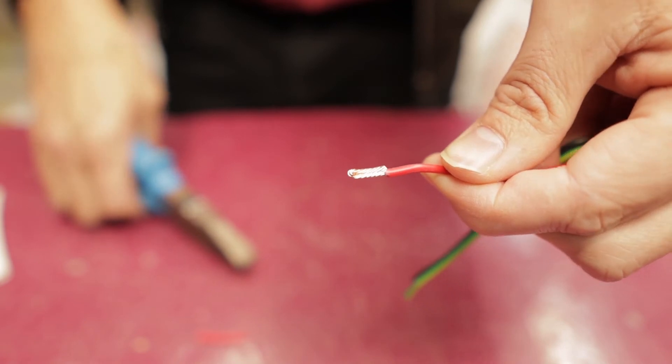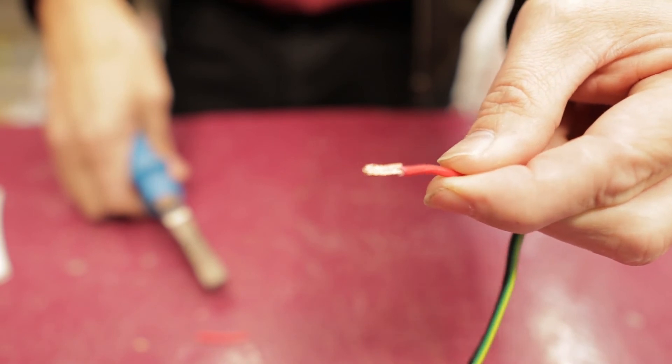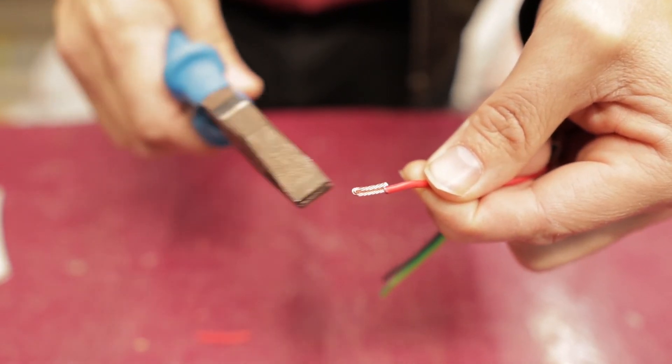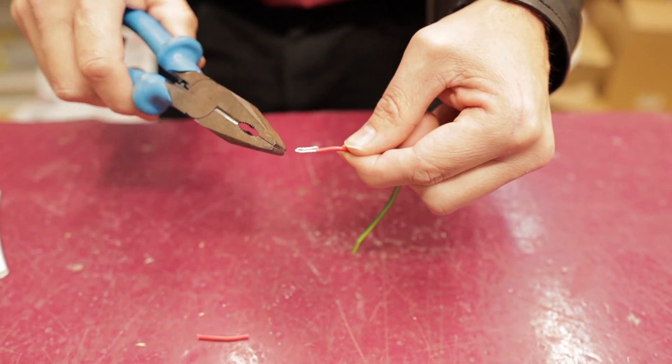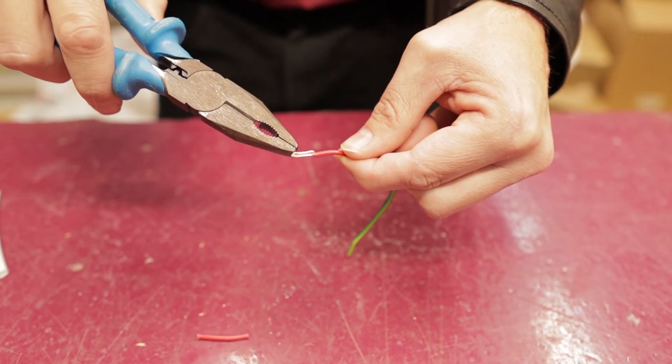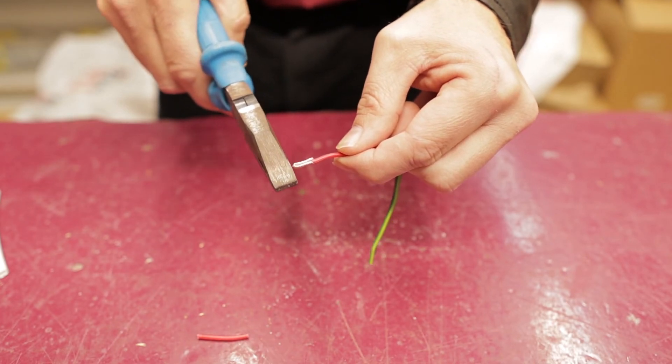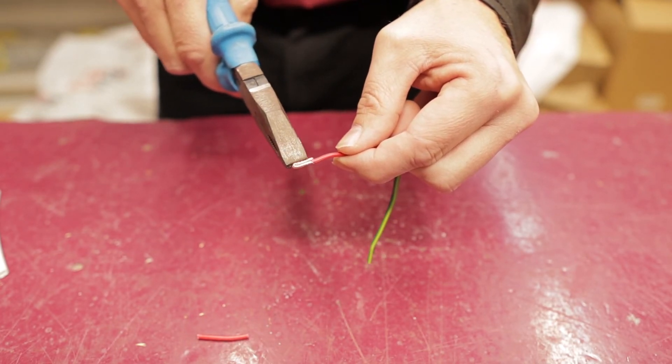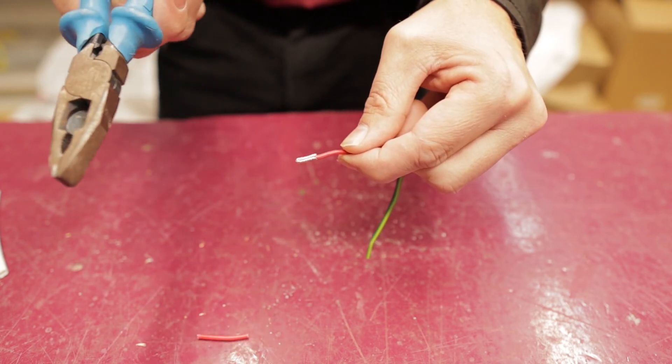And you can see that that wire is nicely wrapped around, it looks like a piece of rope and it is folded over correctly. And it needs to be folded over because when you put it into the terminal block and the screw bites down on that wire you want it so the screw cannot slide off either way. So if there's that bend it'll bite into the middle, push them apart and it'll grip that wire which is what you want.